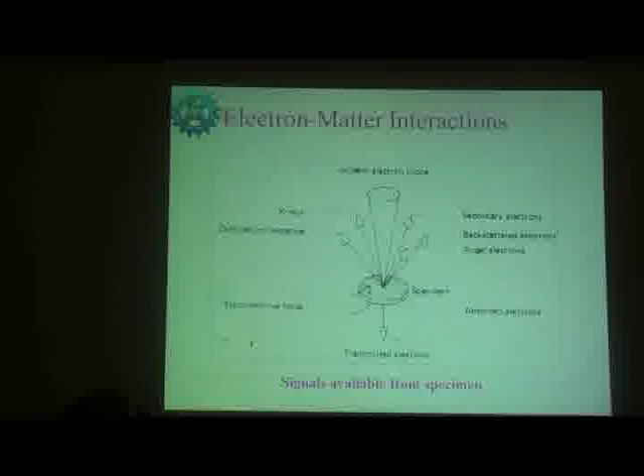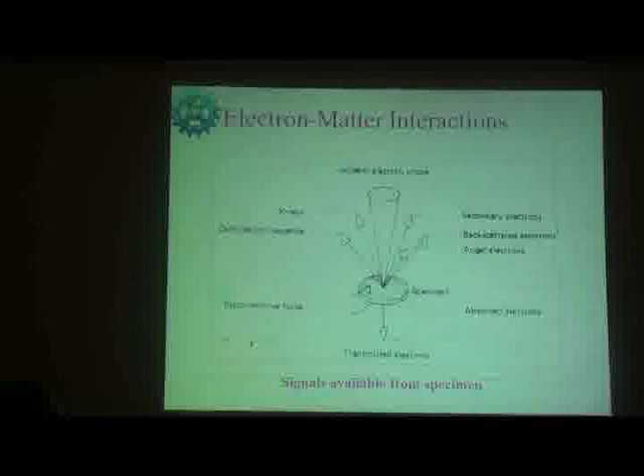In the case of a transmission electron microscope, the electrons are transmitted through the sample. In that case your specimen should be very thin and the beam should be very high energy, something like 300 kilo electron volts. Then the beam will penetrate the sample, and you get crystallography information, particle size and many other things dealt with by the transmission electron microscope.